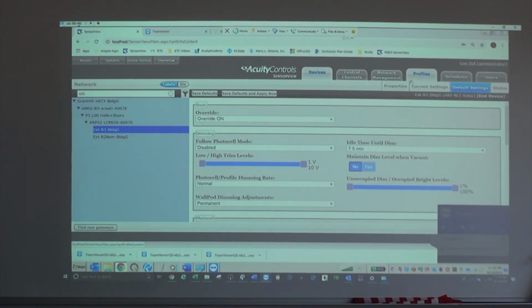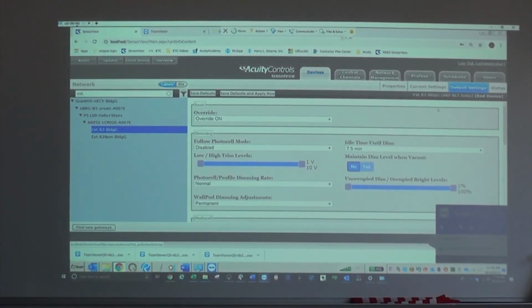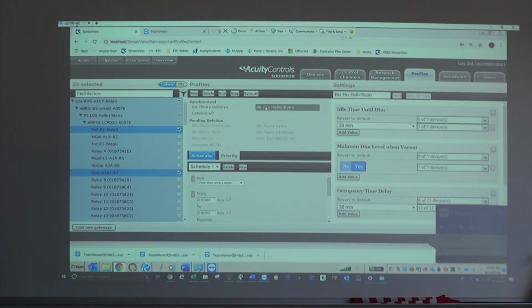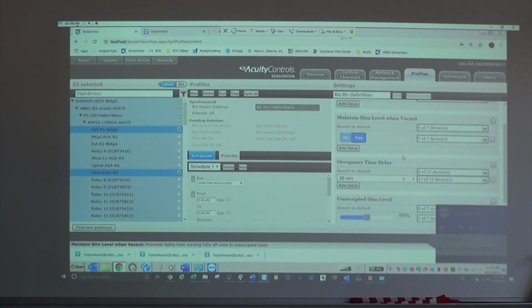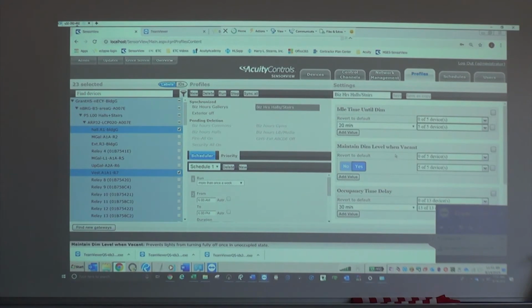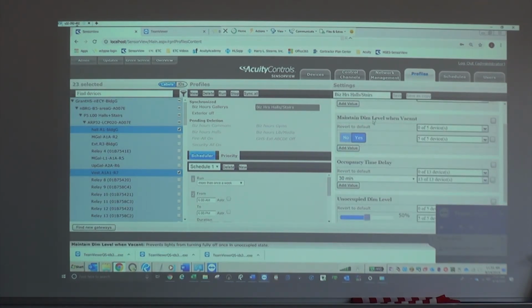The default state of our system is for unoccupied time. So looking at the profile for business hours for halls and stairways, it is overriding the default state where things go off and then come back on. We override it with these settings, the specific and only settings it's overriding during this time. So the idle time until dim changes to 20 minutes, and maintain dim level when vacant turns on, because we don't want the lights to turn off, only to dim to a certain level, because this is what we were told to do.